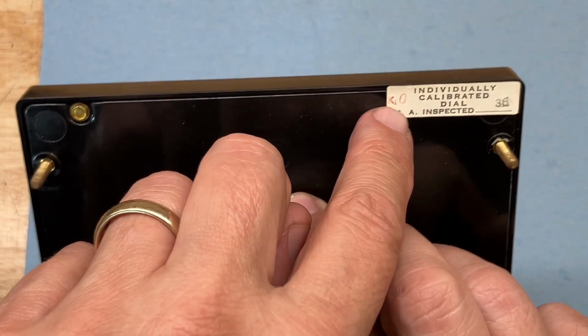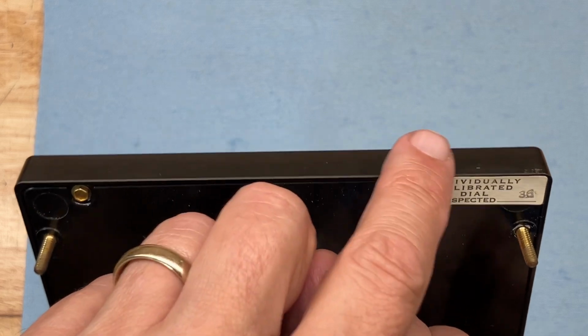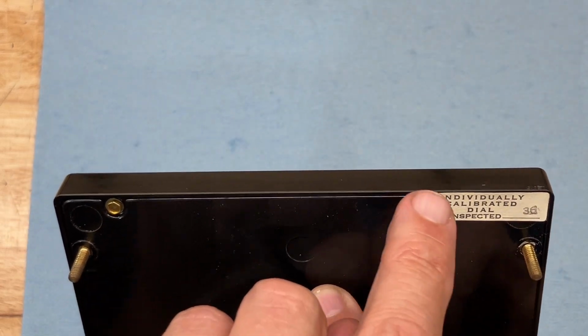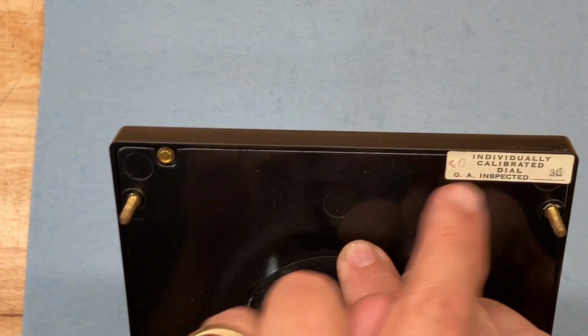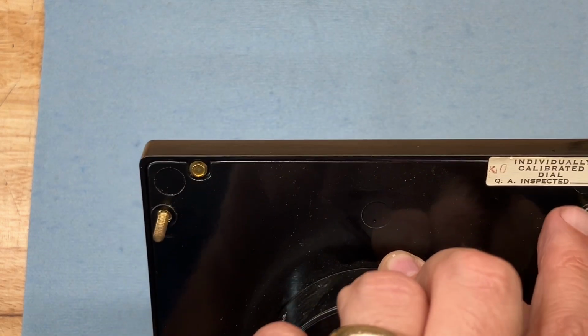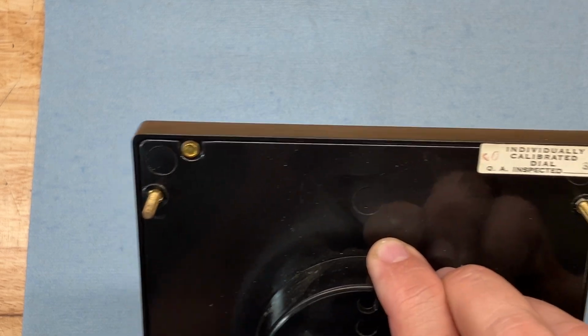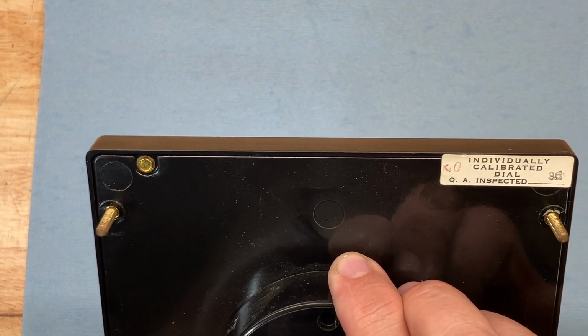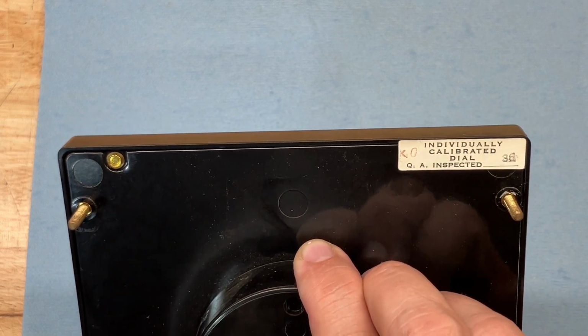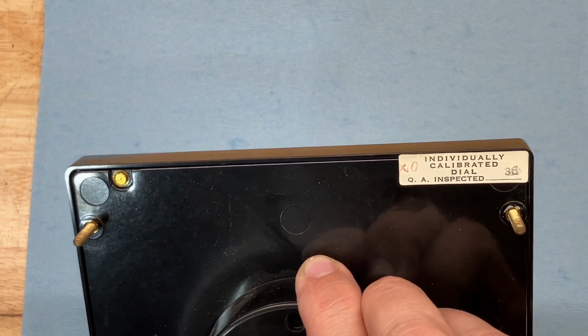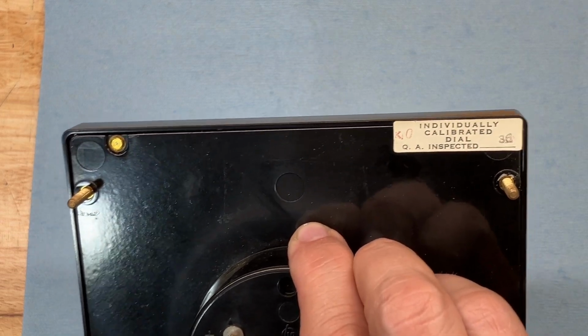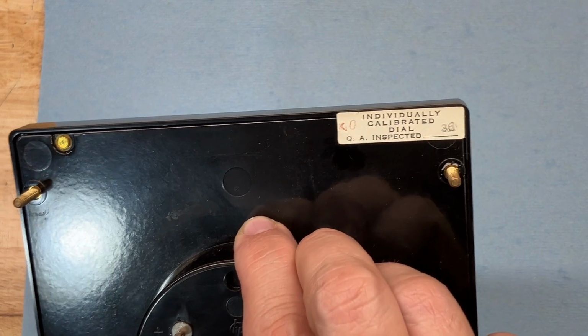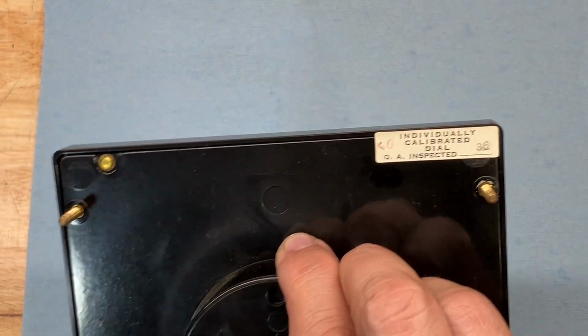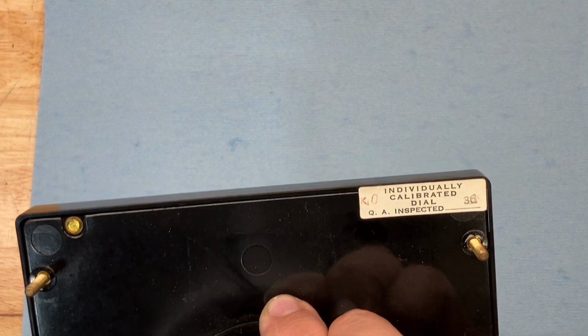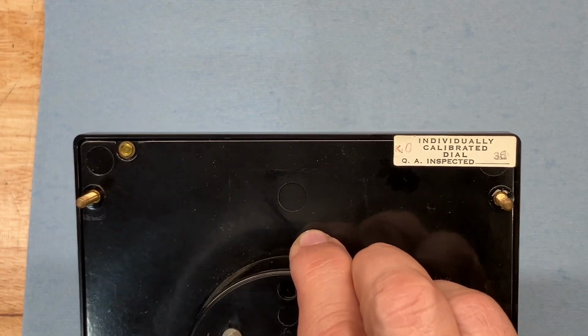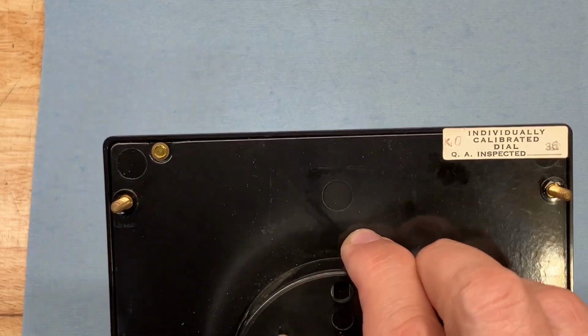There's an individually calibrated inspection label here, which I'm going to try to carefully peel off because it's covering up the screws that hold the meter movement together, and try to preserve it so that I can glue it back in place once the repair is completed. Oh, by the way, I did find date codes on all of the tubes, and all of them say a date code of mid to late 1970. So that's when this instrument must have been manufactured, around late 1970. Not really 1969, but close.